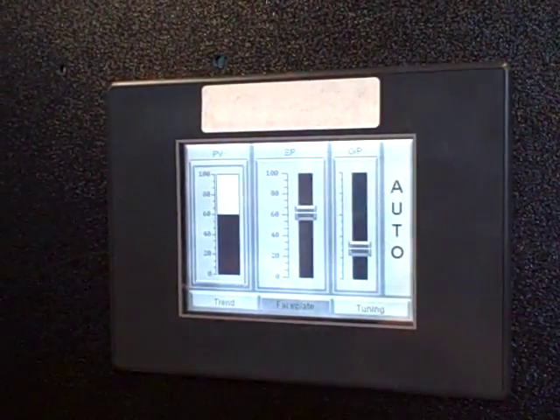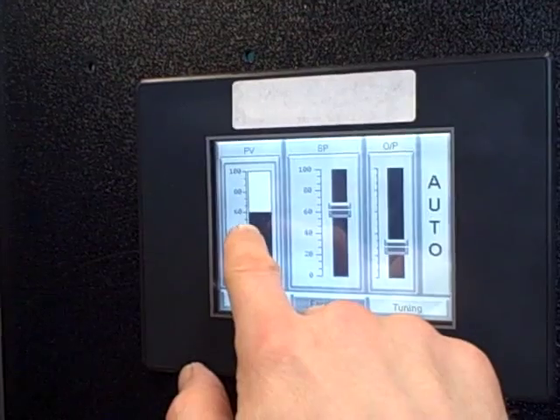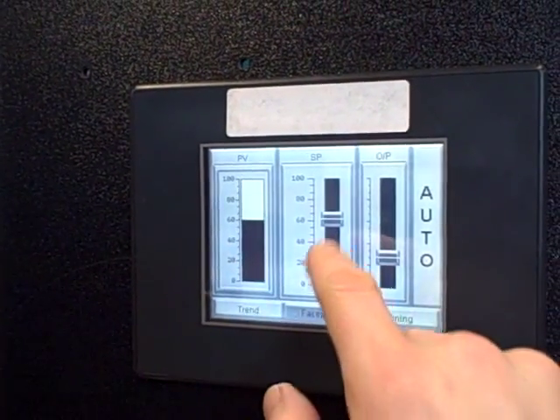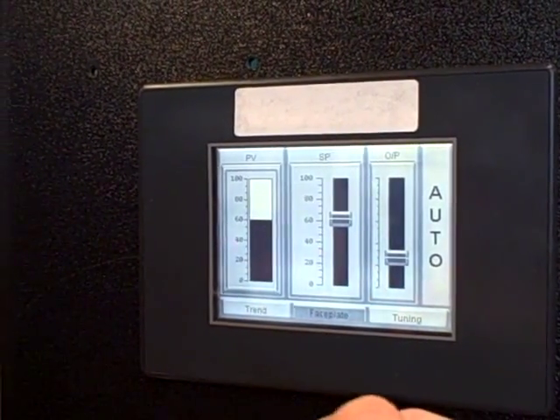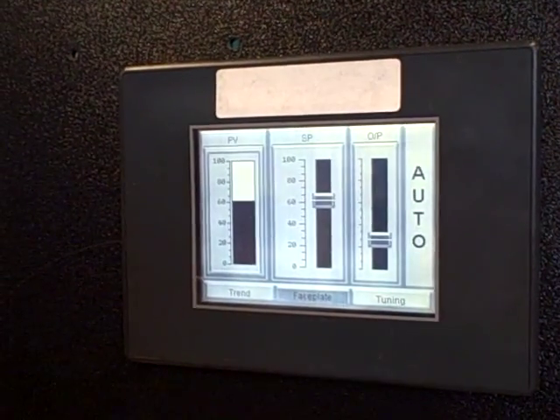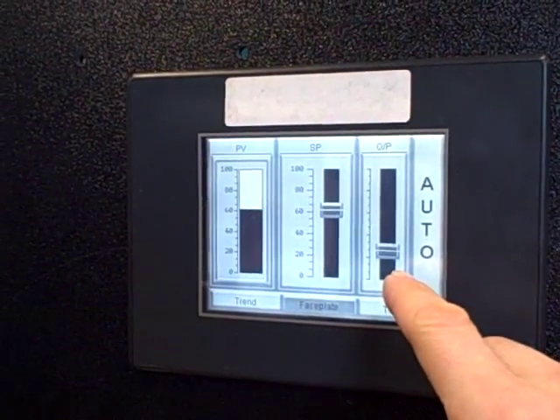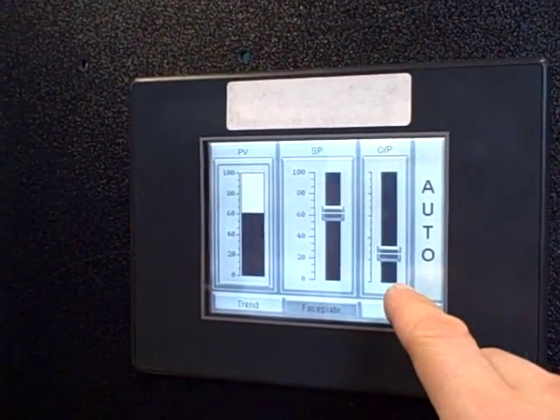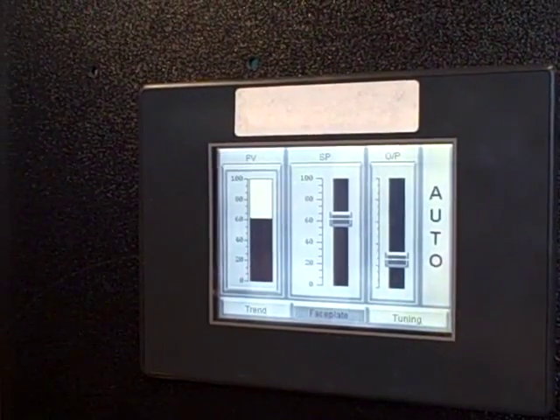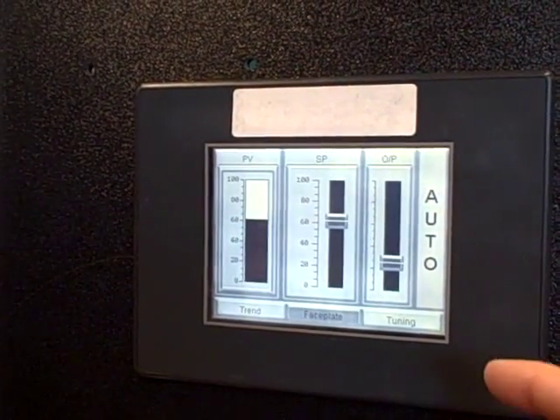On the faceplate, we can see this as well. My process variable is about 60%. My set point is a little bit over 60%, and that's out of a 0 to 500 degree range. My output down here is approximately 25% or so, and we're in automatic mode.